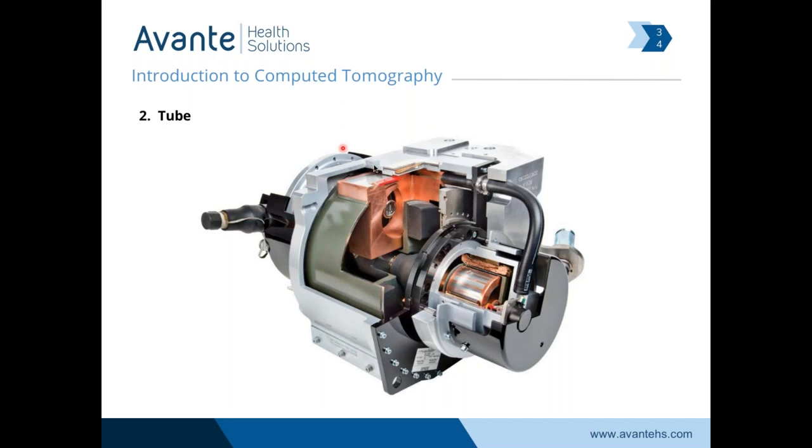Here's a picture of the x-ray tube itself, showing some cutaways of the different pieces. The high voltage cable comes in, with some cooling. The x-ray tube spins very, very quickly. The x-ray tube has a tungsten filament and a target. The tungsten filament takes the high voltage, heats up, the tungsten shoots electrons off, hits the target — which is spinning very quickly — then releases x-ray and shoots it out the output window. On GE x-ray tubes — the MX 165, MX 200, and MX 240 — that number refers to the diameter of the target in millimeters.